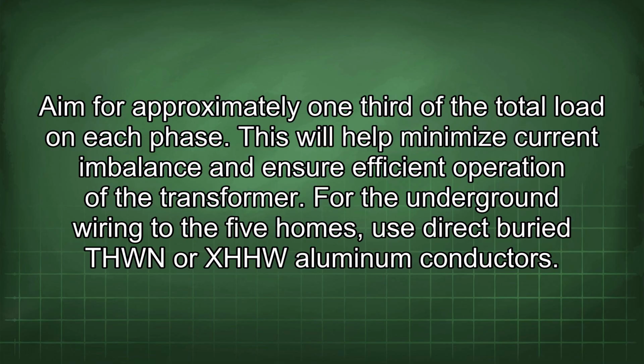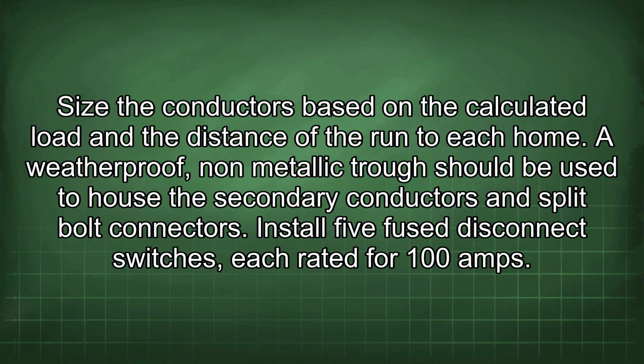For the underground wiring to the 5 homes, use direct buried THWN or XHHW aluminum conductors. Size the conductors based on the calculated load and the distance of the run to each home. A weatherproof, non-metallic trough should be used to house the secondary conductors and split bolt connectors.